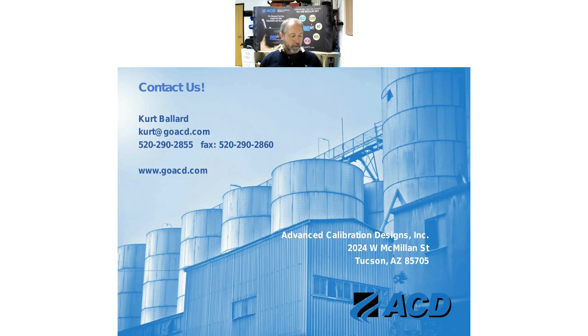I've got a question from Ravi: how much hydrogen chloride, as ppm level, can we get from the QC 100 vials? We usually rate them at about 5 ppm. These things are not real accurate. It depends on how warm it is, but about 5 parts per million at standard temperature, 72 degrees or 20 degrees Celsius, each. Okay.